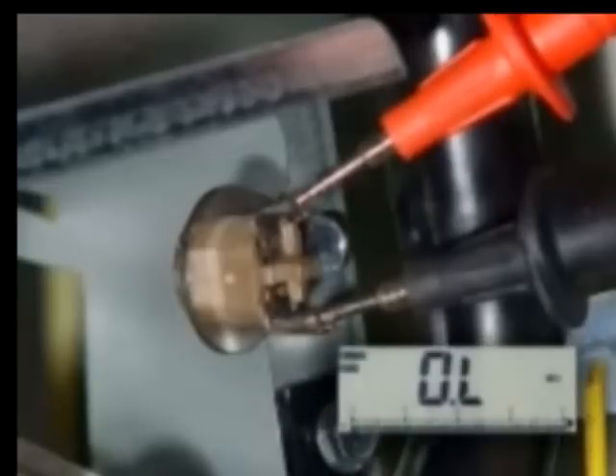If you measure infinite Ohms, reset the switch if it is a reset type. If it cannot be reset, replace the switch.